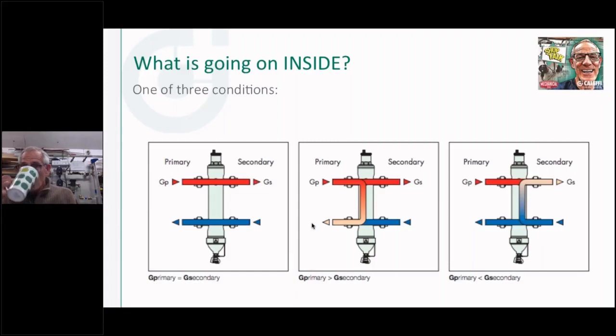Excuse me. And that could change. Let's say I'm using some of the newer pumps that we have out now. Maybe I've got a variable speed pump over here, and that speed is going to change based on zone valves opening or thermostatic radiator valves opening and closing. So this flow can always be changing over here. It can modulate based on the pump speed or whatever it might be. That's changing the flow rate going out to my distribution. So then this number here is going to change based on what that mixing is. And we've got a formula for that. It's called the mixed temperature formula. You need the two temperatures, you need the flow rates, and you can calculate what this number would be if you put that into the formula. If you know the flow rates and the temperatures, I can predict what that's going to be.